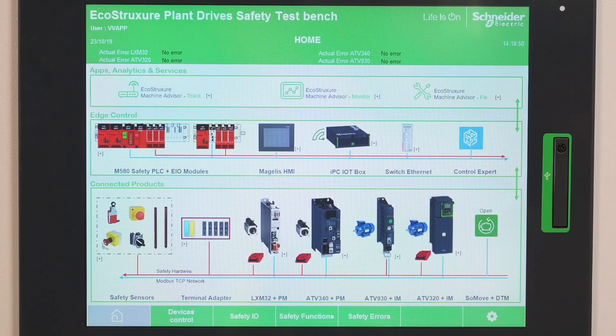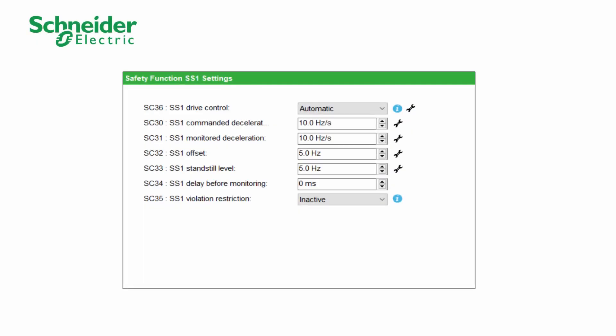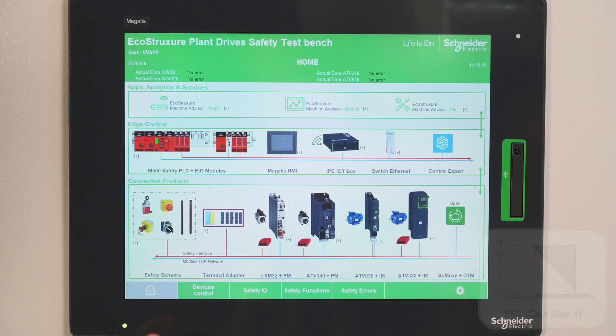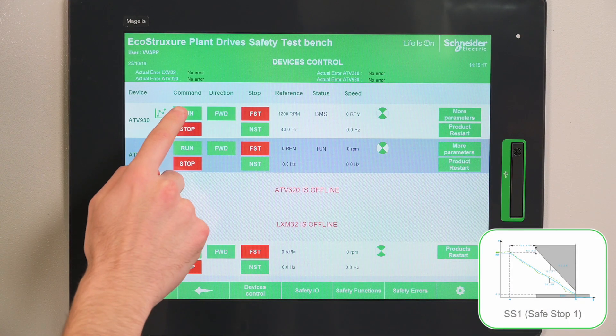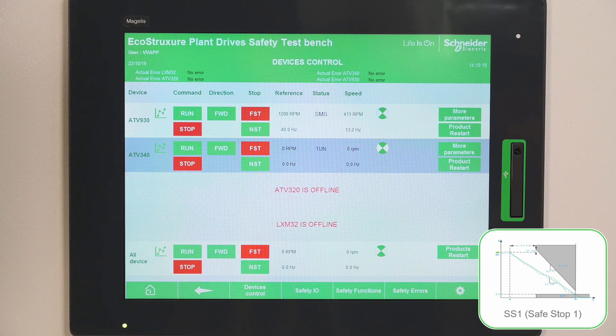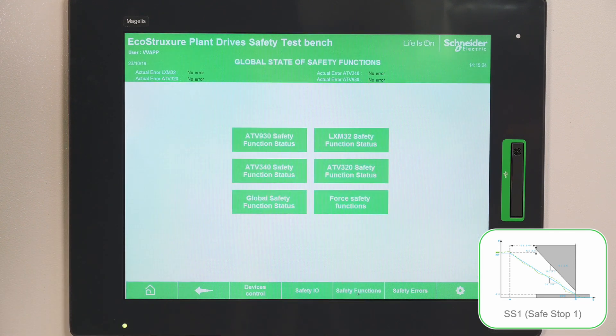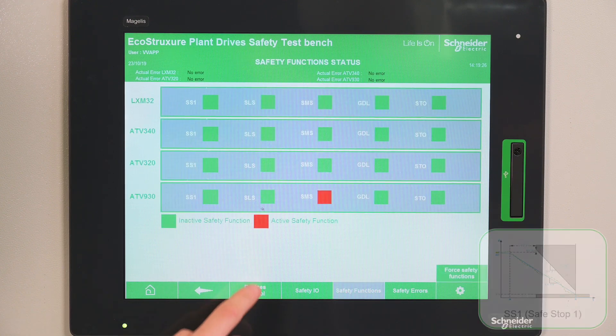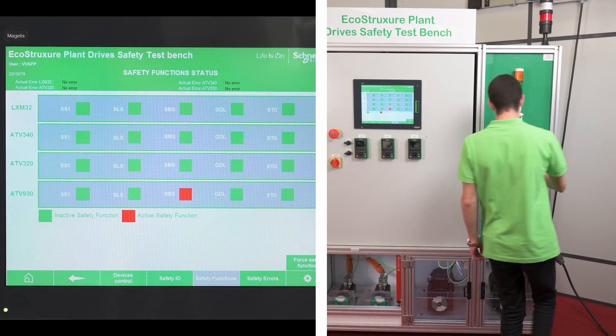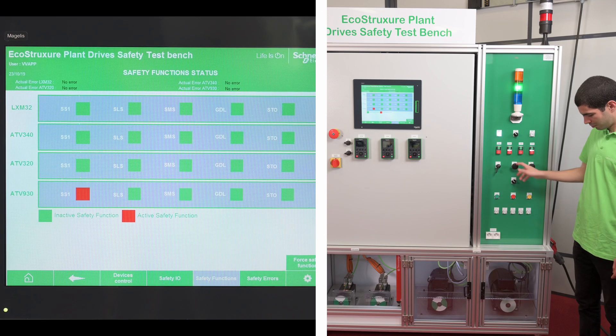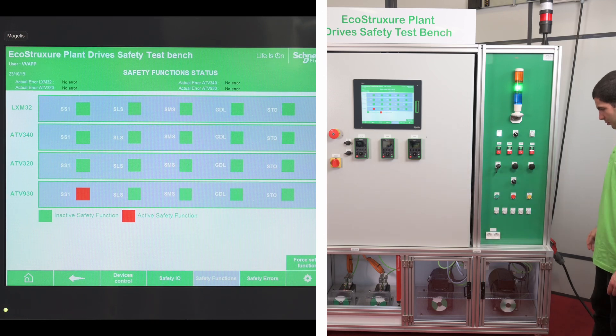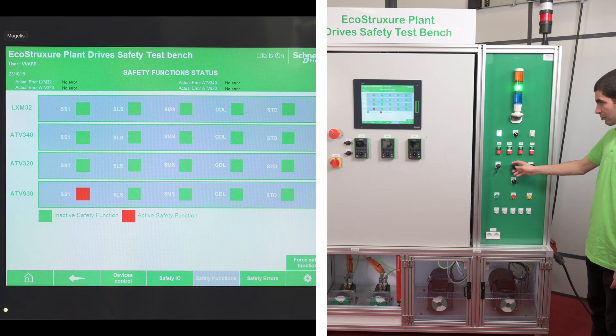The terminal adapters synchronize with the safety module to activate the ATV drive safety functions. We configured SS1 using SoMove. Now we activate SS1 using an emergency stop. We can see the motor stop in Safe Stop 1 using the Safe Deceleration ramp, and we can see activation of the SS1 function on the HMI.